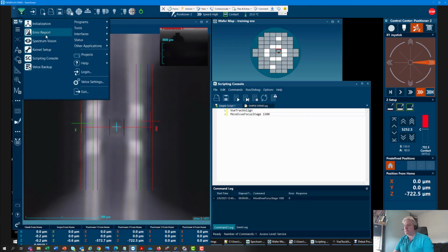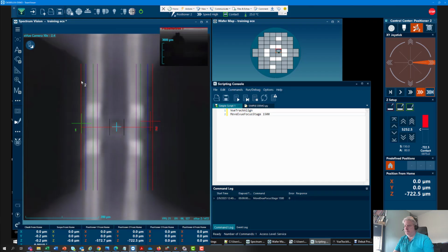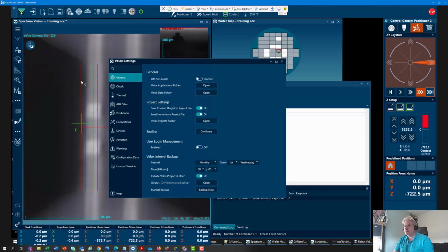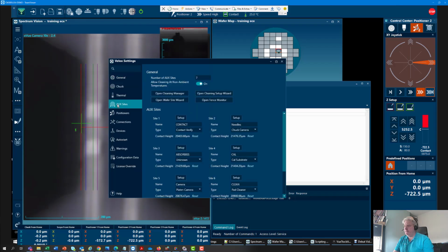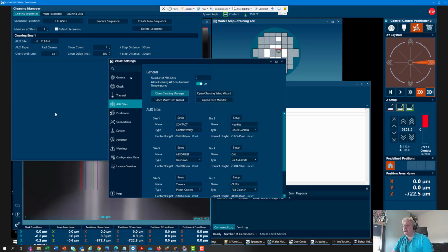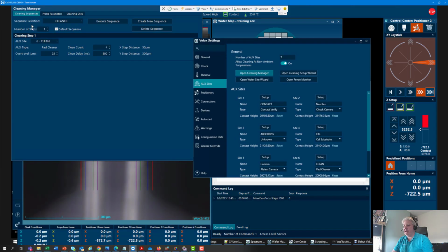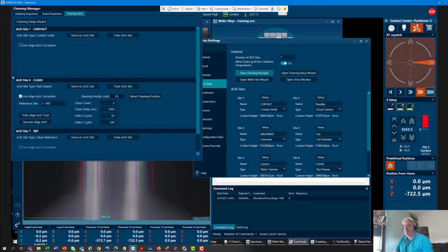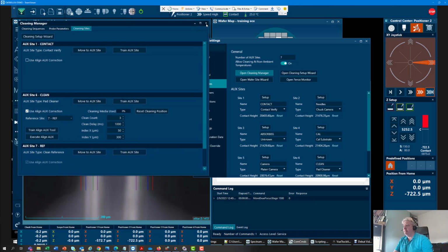If I go to the Velox settings, I can go to the AUX sites, and we have this thing called the cleaning manager. In the cleaning manager, we determine how we're going to clean. So we're going to clean using AUX 6, which is my pad cleaner. I'm going to give it 4 cycles of 800 milliseconds each with a 25 micron overdrive. So that's all been set up. The cleaning sites you can see in use, we're going to use site 6. It's got align AUX correction on, and we're going to use a reference site to find that when we're at temperature. So let's go to setup.